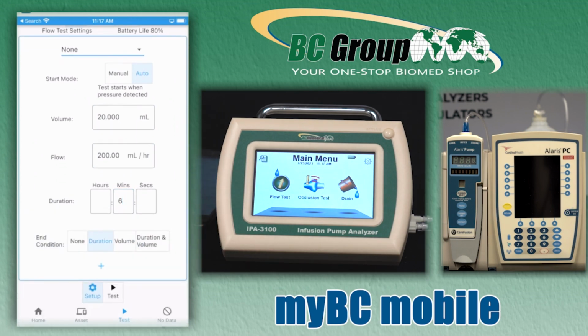So we have an option at the bottom for how do we want to end the test. I can select no automatic end. That means that I have to stop the test manually. Or we can stop the test when we hit our duration of 6 minutes and we can compare our measurements. Or we can do volume. If I pick volume, then it will run until it measures 20 milliliters of fluid, and then it will give you a result based on what it measured for flow rate and volume.